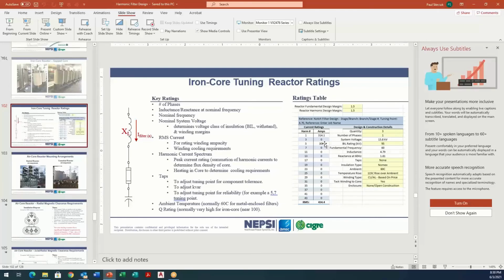I would take 100 times the line-to-line voltage times the square root of 3. That would become my reactive power rating of that filter stage. But then I would rate the harmonic current at 100%. In other words, the fifth harmonic equal to the fundamental. That would then become a relatively conservative design, because it would allow my harmonic current to grow by another 50 amps, by another 50%. So that's just the way we would typically approach a conservative design if we know the values of current.